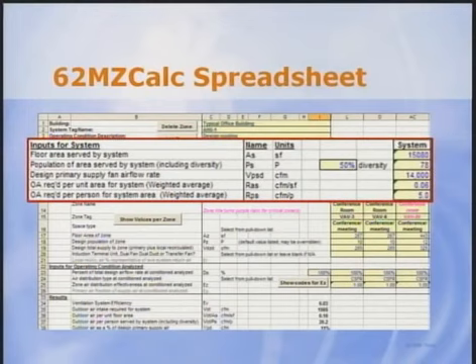All of the cells must be overwritten if you choose not to enter all of the zone data below, but more on that in a minute. If all zones are entered in the spreadsheet, you still will likely overwrite cell I9 for VAV systems, since the sum of zone airflow rates generally exceeds the design fan airflow rate due to diversity. Diversity also applies to occupants. In this case, the actual number of people expected in the area served by the system is half of the sum of the people in each zone. This level of diversity is not uncommon, since at the zone level, every conference room is assumed to be fully occupied, each private office has 2 occupants, the lobby's full of people, etc. It is not likely that all these spaces will be at the peak occupancy concurrently.